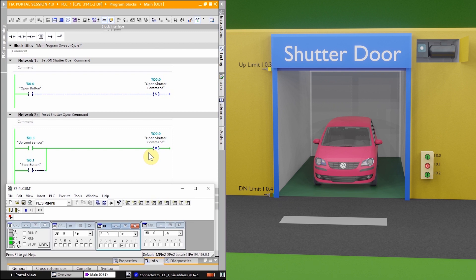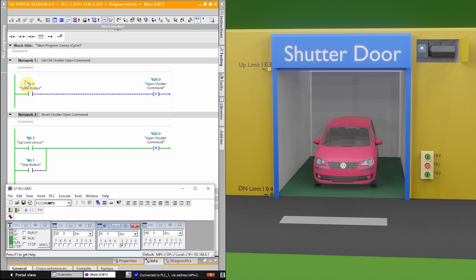One important thing to note: the Reset command has priority over the Set command. This means that if the Reset command is active — for example, when the shutter is fully open — even if you press the open push button I0.0, it will not turn on output Q0.0. As you can see on the simulator, pressing I0.0 does not turn on output Q0.0 in this state.